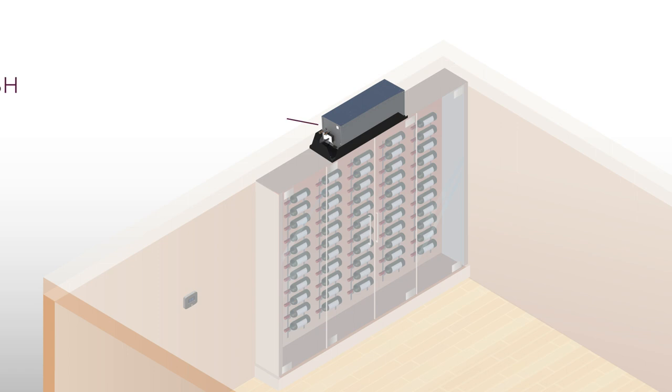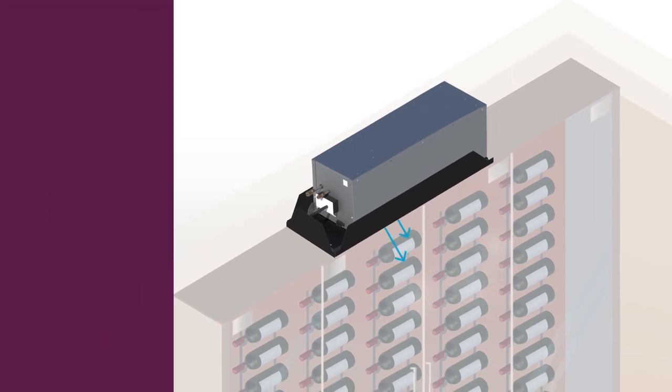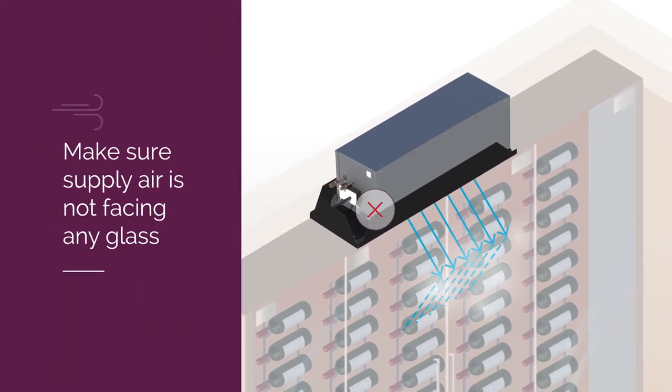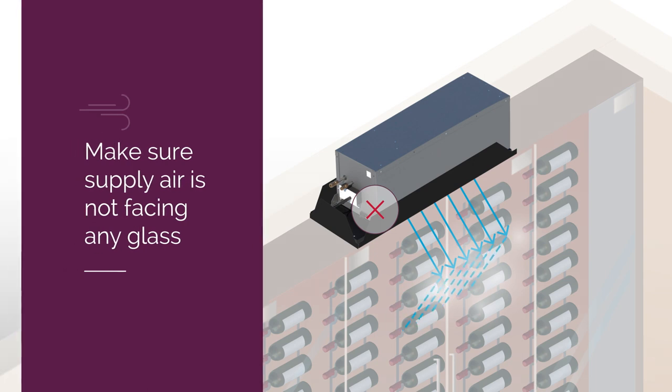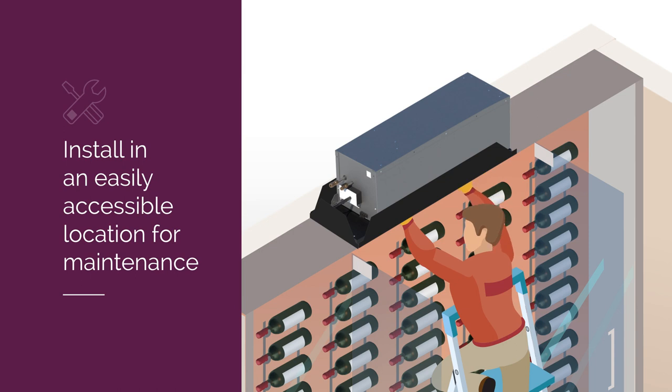WineGuardian wine wall cooling systems mount completely flush with the ceiling in a wine wall. For these and other ceiling-mounted units, it's important to make sure your supply air is not facing any glass to prevent condensation. You'll also want to make sure the system is installed in a location that can be accessed easily for maintenance.